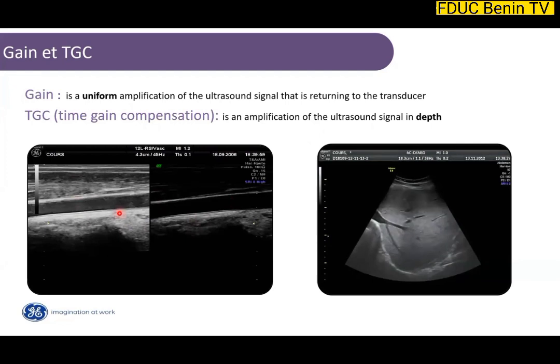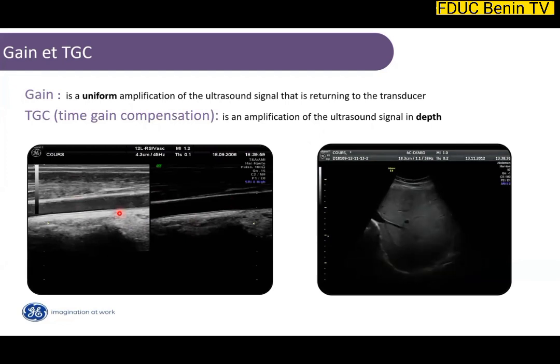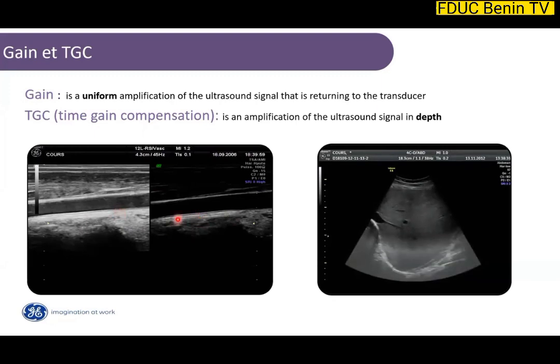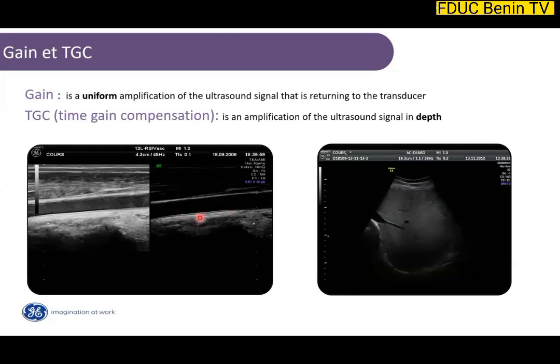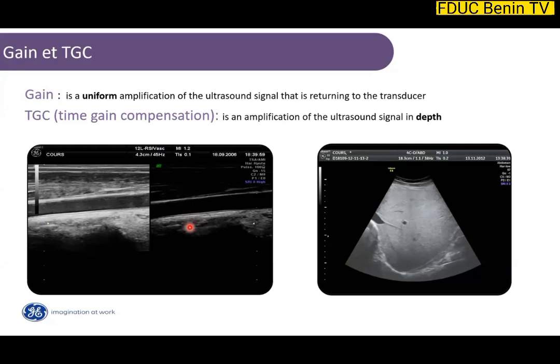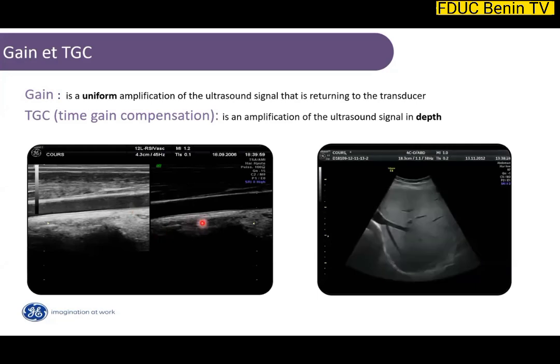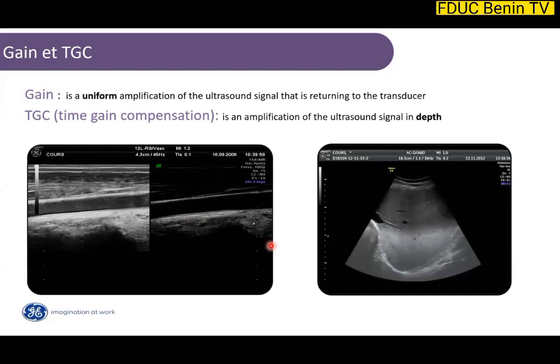And you see, I don't always have to increase the gain. Sometimes I will need to decrease the gain to have a better visualization. For example, here I took the example of a vascular structure. I have decreased the gain of this image just to be able to see clearly inside the vascular structure, and also I can see very clearly the intima media here, because I have reduced the signal. Sometimes I will need to increase the gain to have more signal. For example, when you have a hard to scan patient with a high BMI, you have to decrease your gain. Why? Because usually the fat gives us an amplification of the ultrasound wave. So we will have to decrease the gain to have a better image.